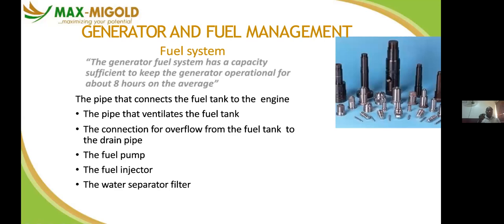So this is what you do for your fuel system. The pipe that connects the fuel tank to the engine, and the pipe that ventilates the fuel tank. When you have a diesel tank, there should be an opening whereby the heat returning from the generator can escape through that opening. If you don't do that, it will cause your tank to expand and explode. It can cause damage to other facilities. So ensure that your tank has an opening, just like a breather hose on a generator, or just like your nose, where you breathe out.